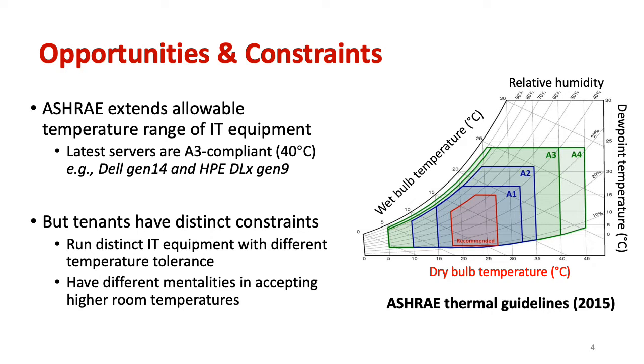Specifically, ASHRAE has defined 4 classes of A1 to A4 for IT equipment to tolerate higher temperatures. Many latest servers are A3 compliant, meaning that they can tolerate an inlet temperature of up to 40 degrees. However, the tenants of colocation data centers may have their own constraints in adopting higher temperature set points. They may run distinct IT equipment with different temperature tolerance. They may have different mentalities in accepting higher room temperatures.